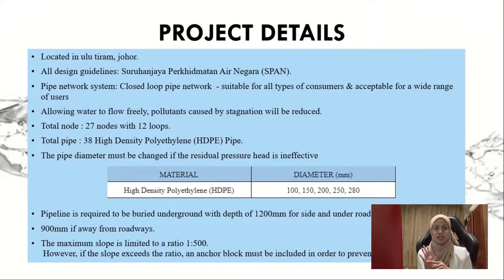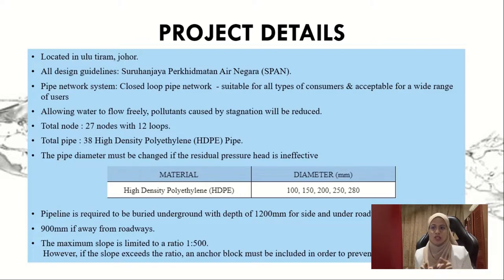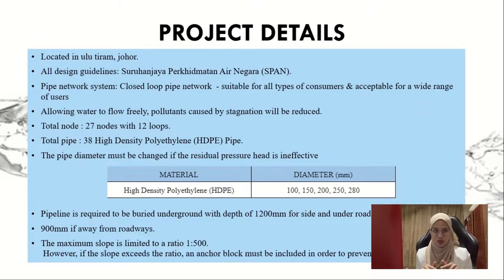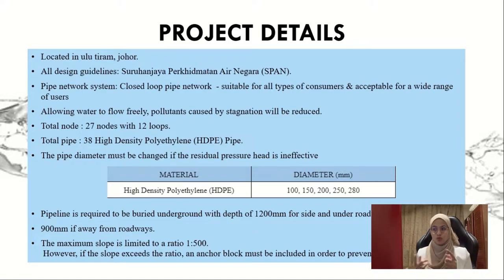As a requirement, the pipeline must be buried underground at a depth of 1.2 meters for the site and under roadways. If away from roadways, the pipeline must be buried below 0.9 meters underground. If there is any slope, the maximum slope is limited to a ratio of 1 to 500. If the slope exceeds this ratio, we must use an anchor block to prevent sliding.